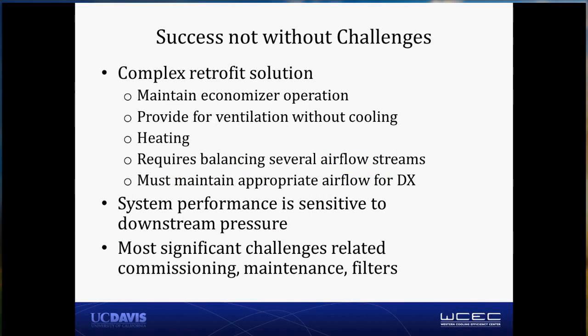So the project was really successful, but there were some challenges. As I named before, the system was pretty complex to retrofit, and we think that there's some opportunity to apply these systems more in a standalone application. They may still need to operate in parallel with vapor compression systems to provide enough room cooling, but it might be easier to install them almost in a DOAS fashion, a dedicated outdoor air supply fashion, where they stand on one end of the building and supply all of the ventilation air, and then all of the rooftop units on the building are constrained to operate in recirculation only. It'll avoid all of the complex physical additions that we had to provide to these 6 rooftop units, though it'll still, very importantly, require some sophisticated controls integration.